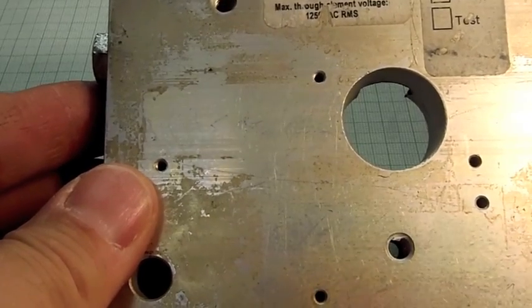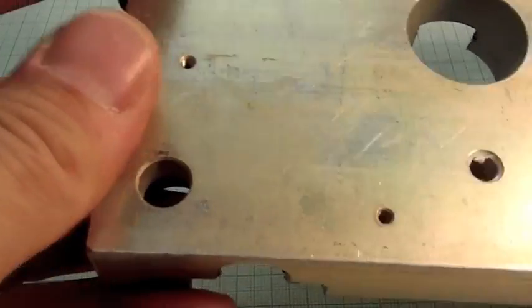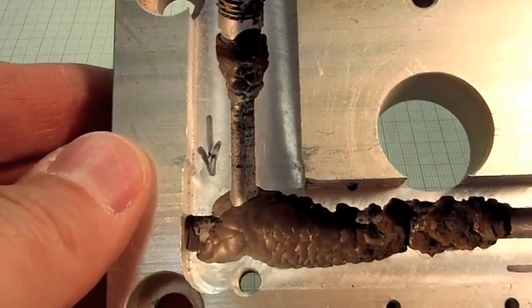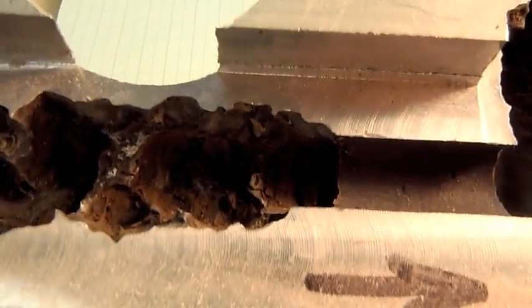This aluminum plate was used as a heat sink for electronic equipment. Cooling water flowed through it. As we can see everywhere the water hit turbulence, especially at these elbows, we had a whole lot of metal loss. This is called erosion corrosion.